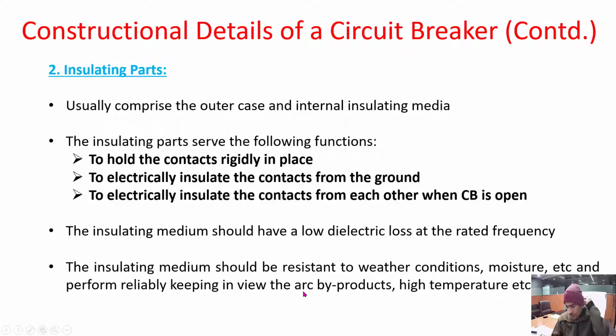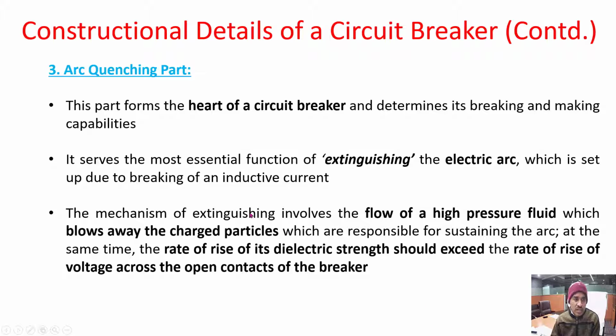There is arcing every time whenever you open. There will be an arc. So therefore, some arc byproducts will be there. And then high temperatures are also expected inside. So therefore, the insulating medium should be resistant to these conditions, weather conditions, moisture, and must perform reliably for a long time in view of this high temperature and arc byproducts, etc. Then the third one is the arc quenching part. This part forms the heart of a circuit breaker and determines its breaking and making capabilities.